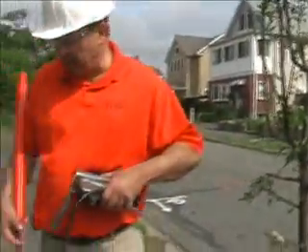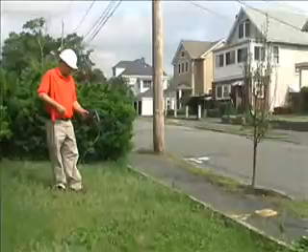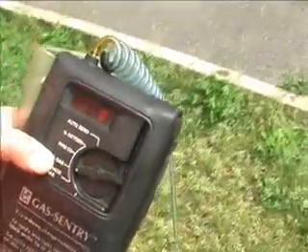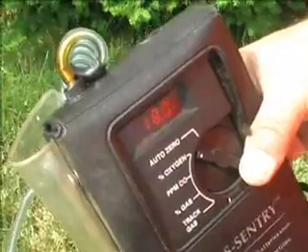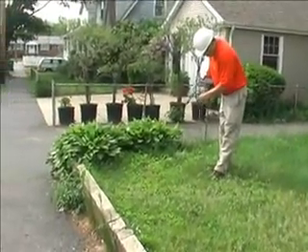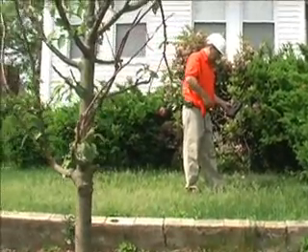Let's make sure there's no gas up in the yard here — I'd like to get a zero. And we have zero gas here. The oxygen level could be beeping from the previous reading; it's 18 percent oxygen, zero gas up in the yard. I'm going to put test holes on both sides to make sure there's no gas migrating up towards this house. The gas company has already been here and checked this for safety. Zero gas — 18 percent oxygen, zero gas at all locations around the house.